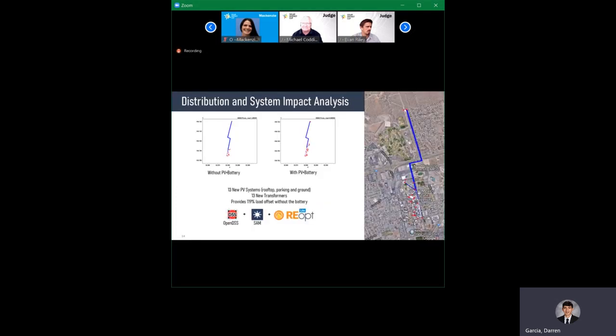In modeling the system distribution impact analysis, we utilized 3 main programs: OpenDSS, used for systems impact modeling; SAM, used to calculate total generation and response; and REopt Lite, used to model the system's resiliency. In the main graphs, we can see the system's circuit diagram before and after the addition of the PV and battery storage. On average, the system can offset about 119% of the university's load, with the additional generation going to batteries.